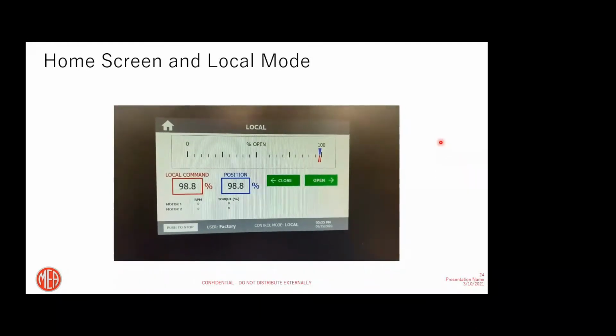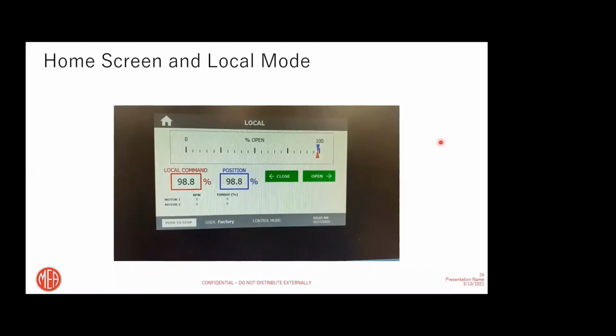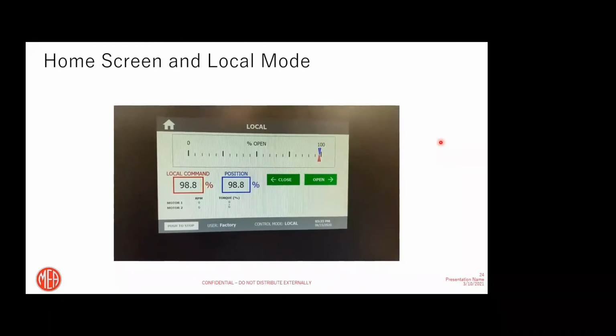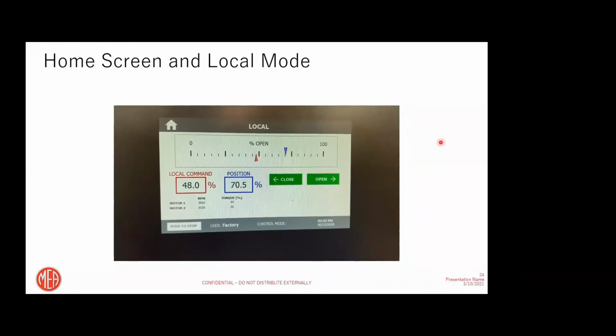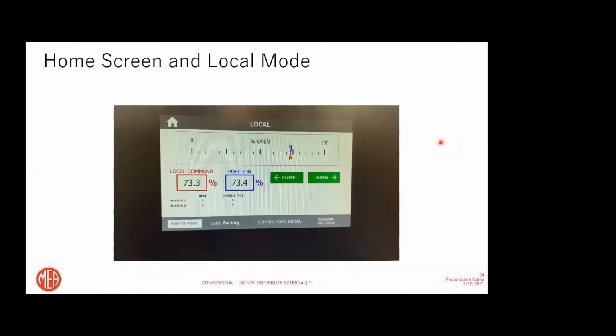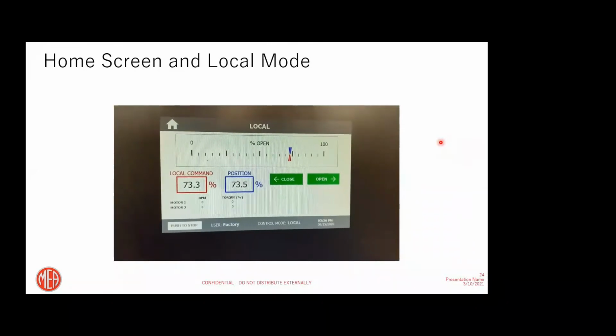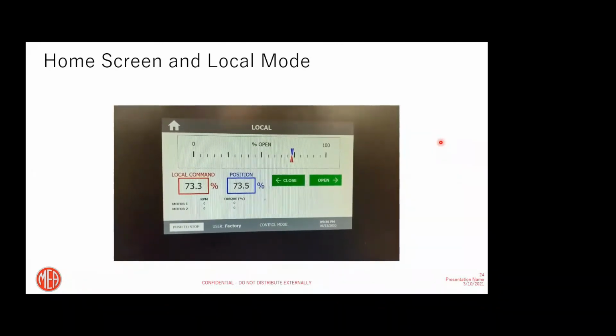We also have motors 1 and 2, which each have a readout of the RPM and torque being output by the motor. Here we'll just drive this back and forth a little bit and get the user accustomed to the screen. One final thing worth mentioning in local mode: you are limited to 0 and 100% as set by the actuator's soft set points, meaning you cannot exceed the set points in either direction. It is not possible to overdrive the actuator and dead end.